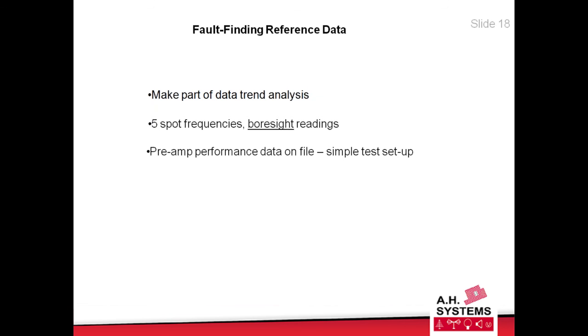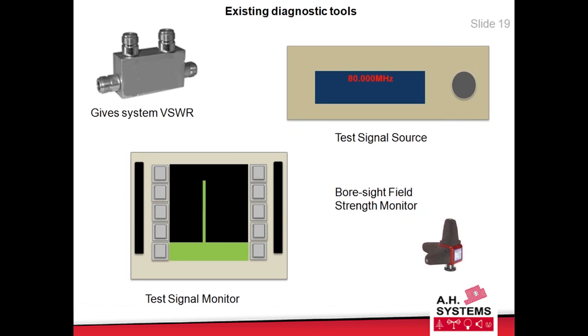You should have the preamp performance data on file - same thing, very easy. Both these procedures stress that you first have to calculate that you're getting less than the damage level of an instrument. If you're using a spectrum analyzer as your measurement instrument, and the no-damage level is plus 10 dBm, you need to make sure you don't exceed that, because the last thing you want when you become self-sufficient at fault finding your own test system is to blow up an expensive test instrument.